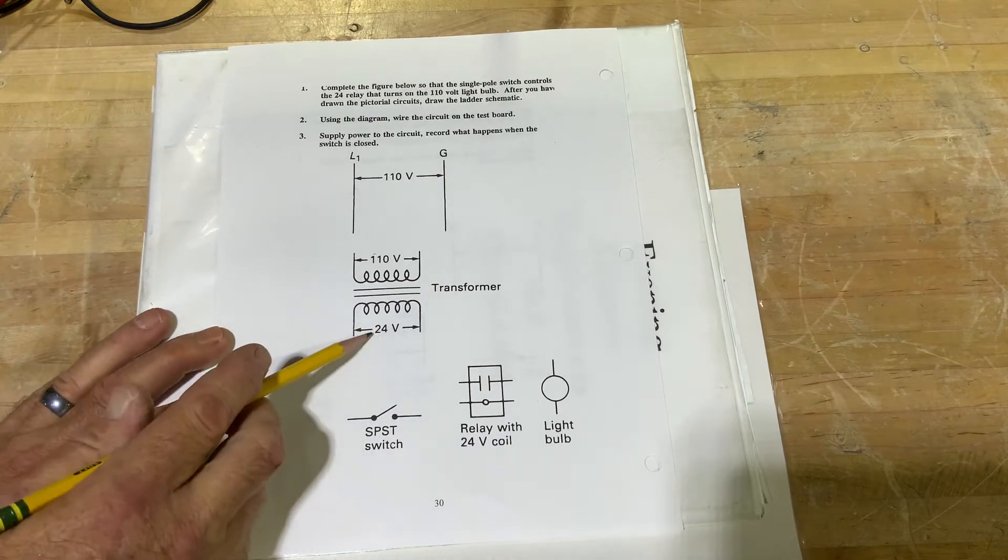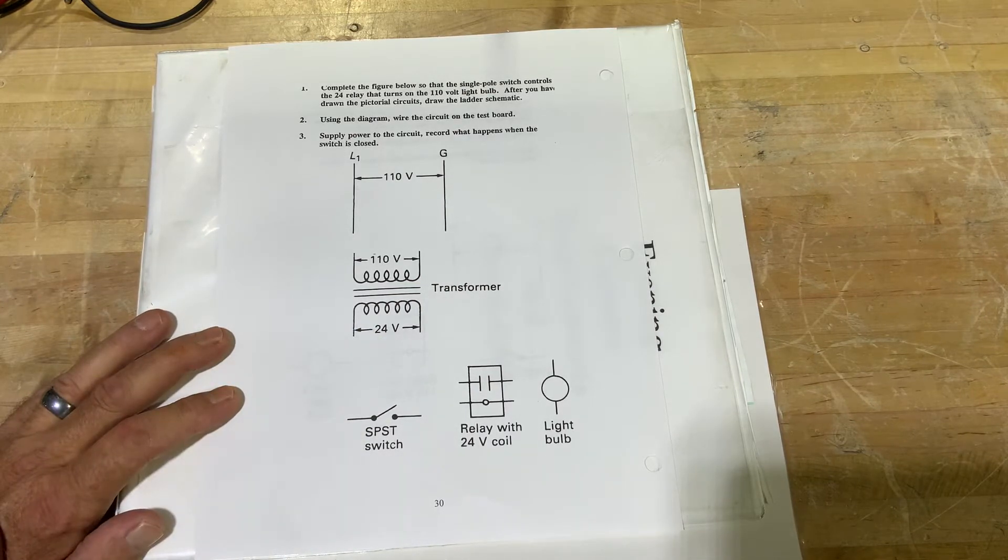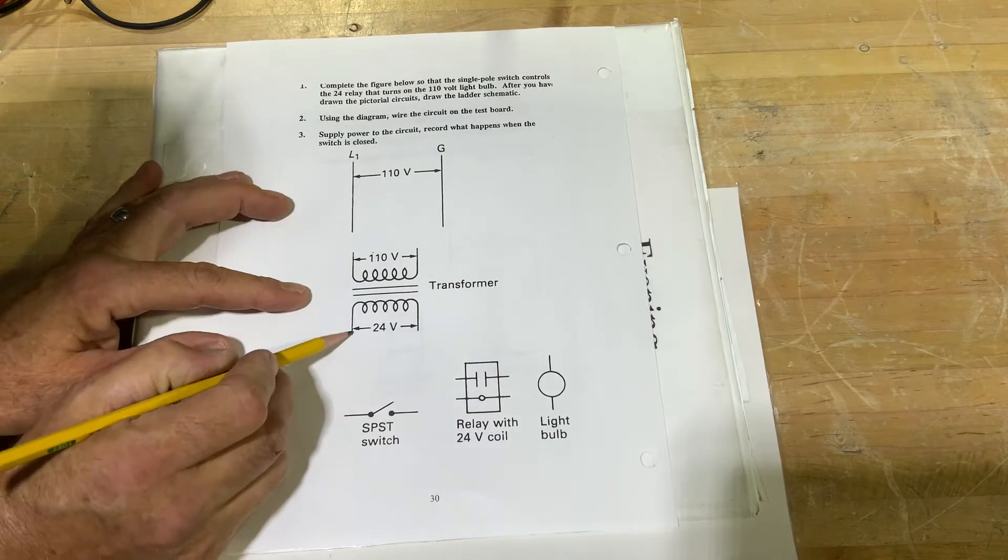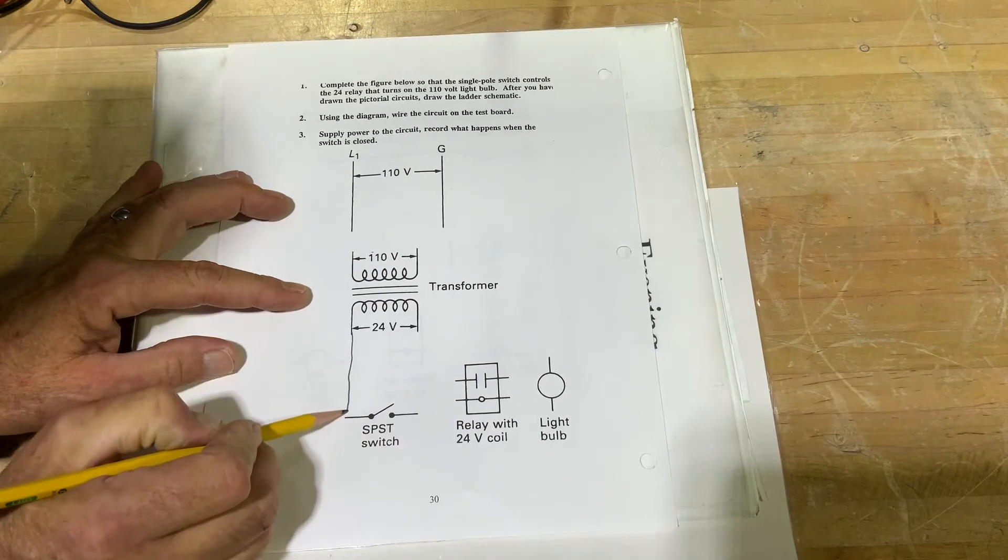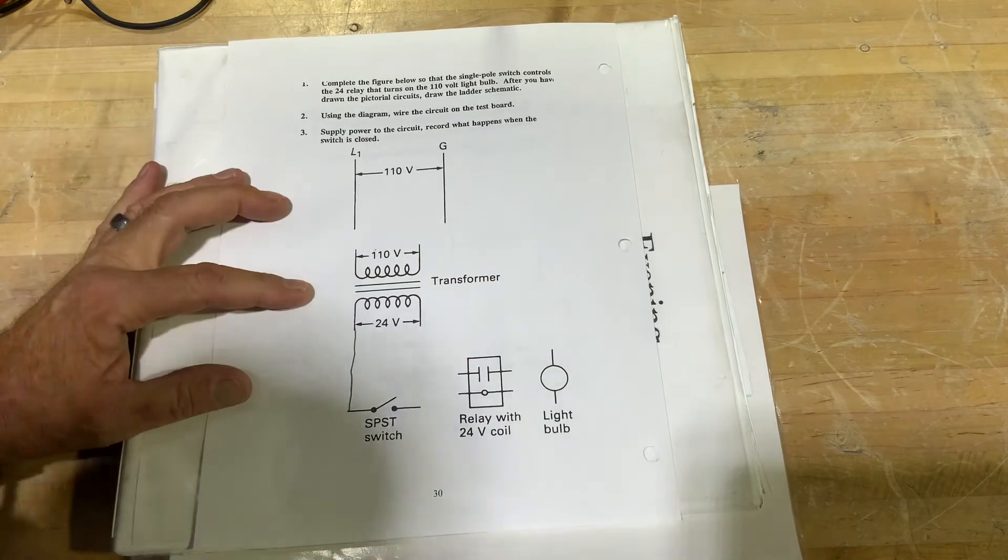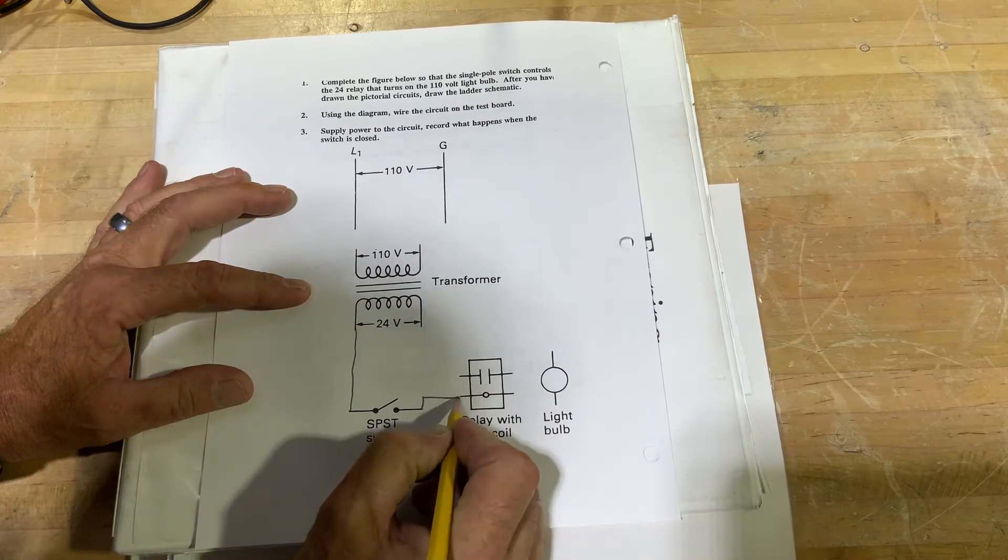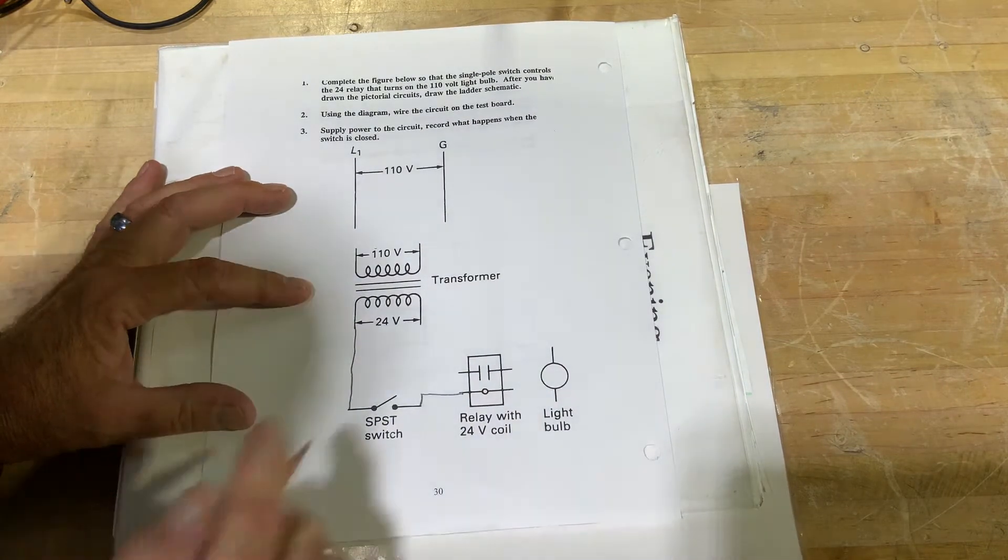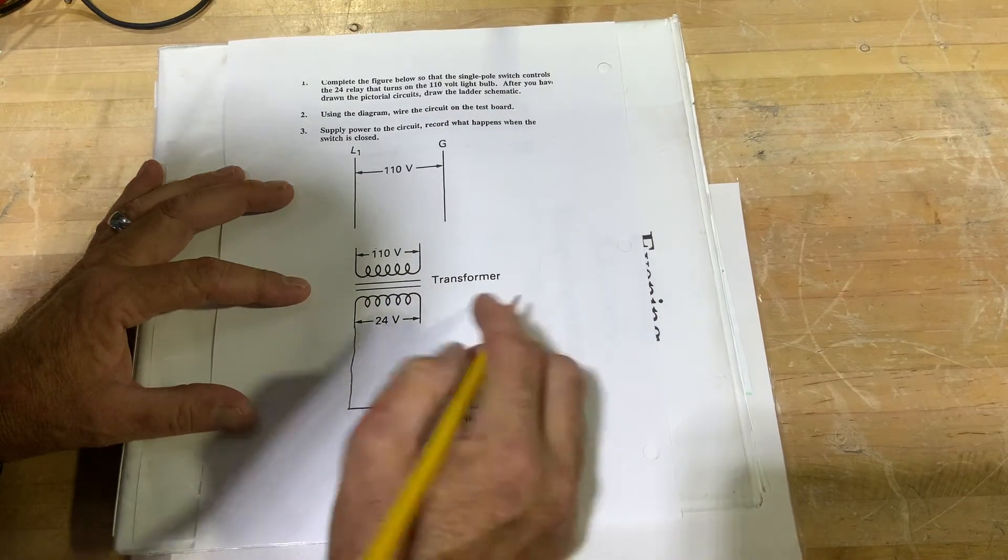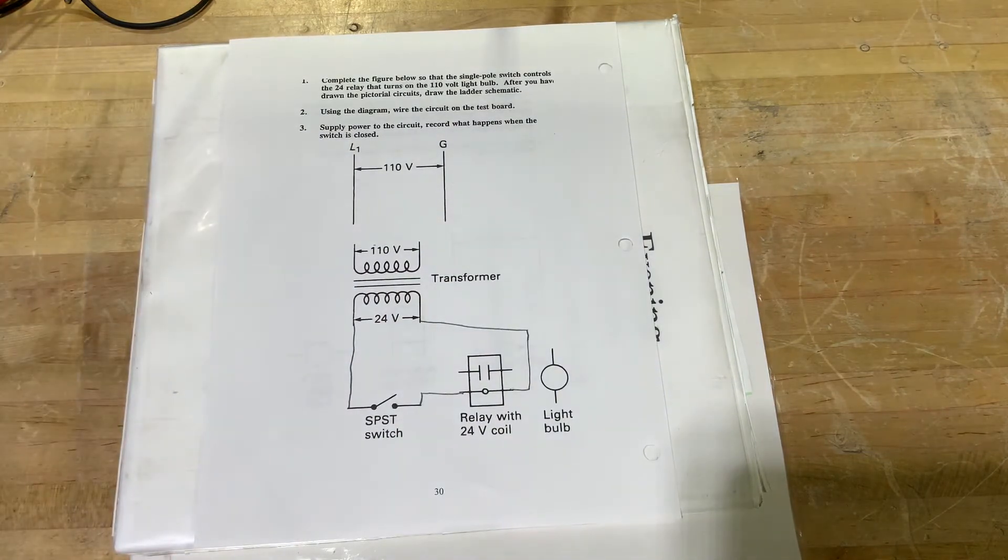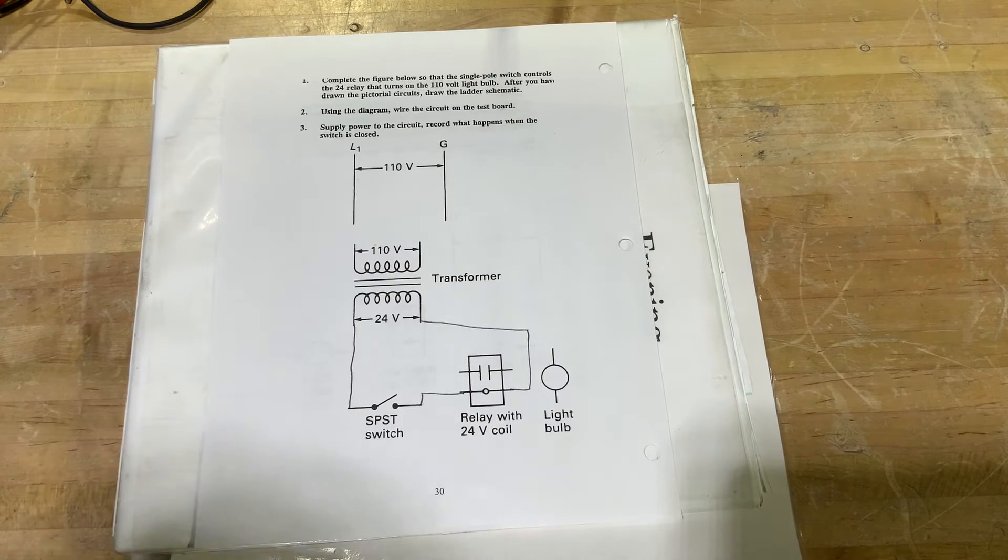We have that single pole single throw switch. We're going to put that on the transformer 24 volt side to control our coil. So we could just take that 24 volt power, go into one side of our switch, out of our switch into our coil, out of our coil back to our 24 volts. So we have that 24 volt circuit wired in.